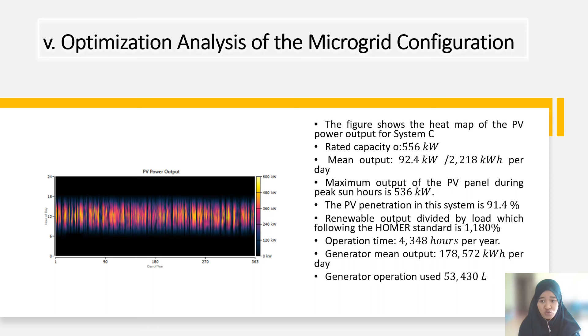Meanwhile, the generator has produced energy with a mean electrical output of 94.5 kW, with minimum and maximum output of 65 kW and 224 kW. The simulation shows that the generator is using 0.299 liters of fuel per kilowatt-hour.